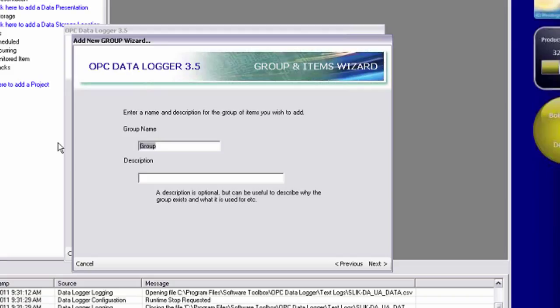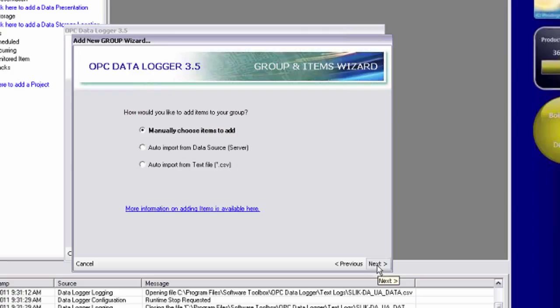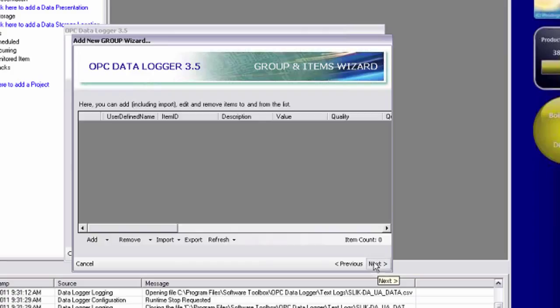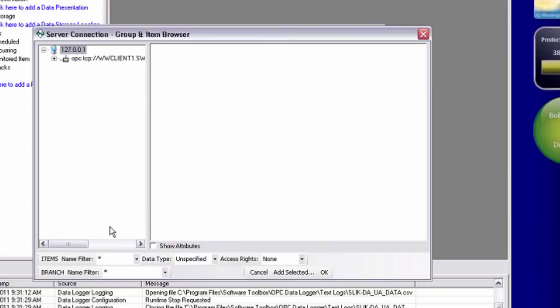I'm going to name my OPC UA tag group top server UA tags. Next. Again, I'm going to keep the default settings of subscription-based at 250 milliseconds. And I also want to manually choose the items I want to log again. So add browse for items to add.